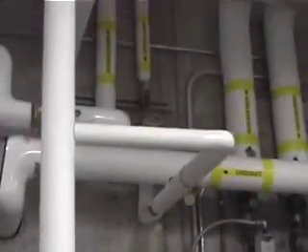I've heard of Legionella, I never really had that come up before. Really? Yeah. I've talked to my plumbers, they all either set our storage tanks at 140 or they surge them. See, the issue with doing it is that out of this tank right here, it goes up to a recirculation pump and goes out to the building. So if I set it to 140, it's really hot water.